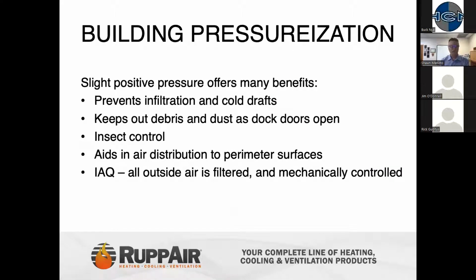So why is building pressurization important? Maintaining a slight positive pressure is critical to really any building, preventing infiltration, cold drafts, and keeping out debris and dust from the dock areas. Insect control is becoming a big part of this. That's why we're going to talk a lot about mechanically pressurizing these spaces.